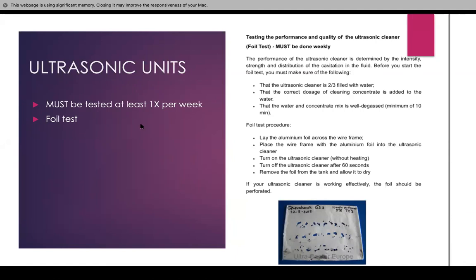You have to test your ultrasonic unit. The ultrasonic testing has to be done at least once per week — we call that the foil test. The ultrasonic cleaner is filled two-thirds with water, and then the correct dosage of cleaning concentrate is added. Every office uses a different one, so look into whichever one you have. The water and concentrate must be mixed well for a minimum of 10 minutes.